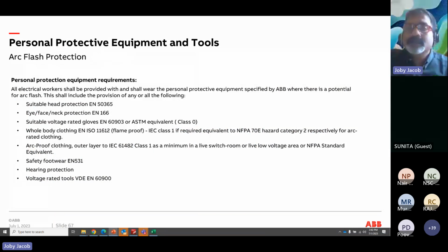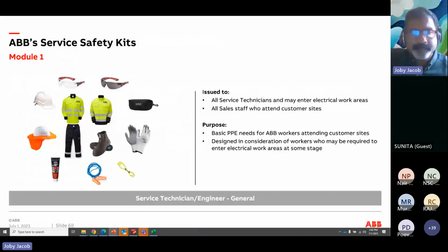It is not only about PPE, it's about head protection, face protection, suitably rated electrical gloves, and EH rated footwear. Normally the EH rated footwear is tested up to 18 kV, so that the outer sole is tested up to 18 kV and you get the insulation resistance in giga ohms, not in mega ohms. Then hearing protection and voltage rated tools. So this is the primary kit for people working live near equipment.